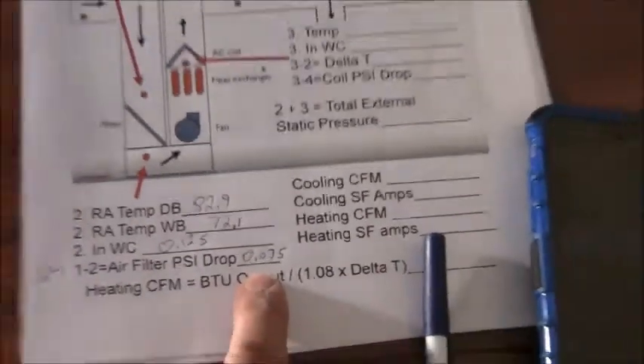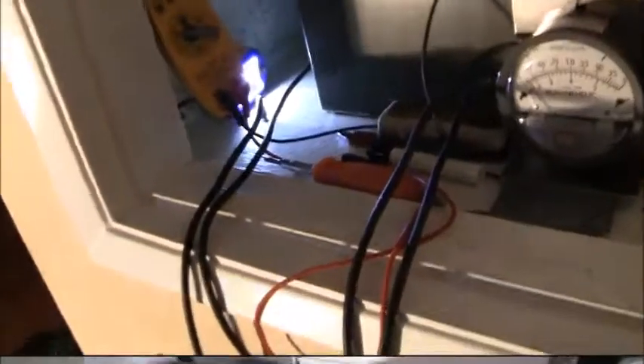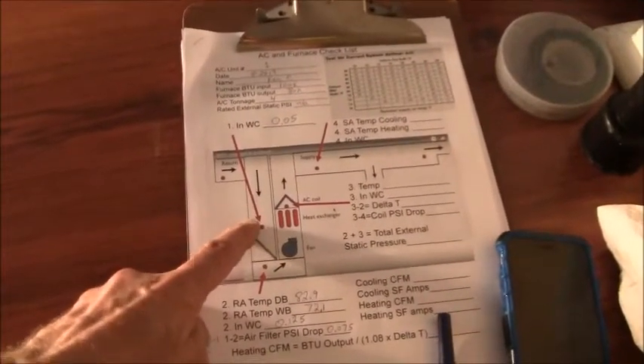Let's do another test. What I want to do now is use the low and the high right across the furnace. So what I'm going to do is take the low, which is right here, I'm going to stick that in before the filter, and I'm going to take the high and put that in after the filter and see if that reading equals this reading right here. That's what I'm going to do right now. I have another needle valve right here, so let me get that out of the package and give me a second. Okay, I got it hooked up so that the high probe is actually here on the system, and the low probe is here.